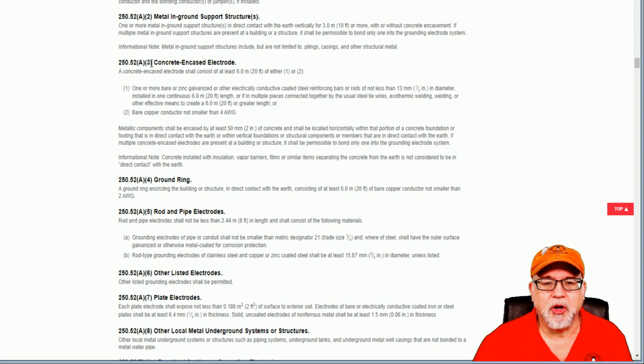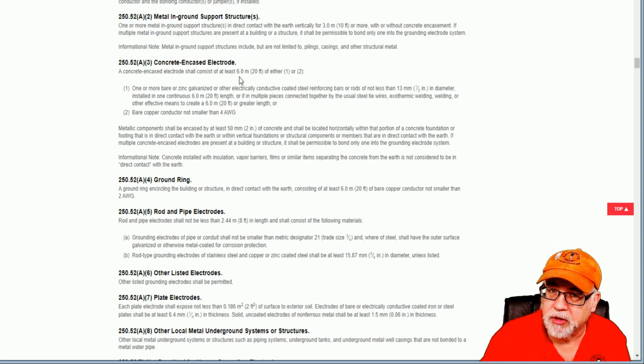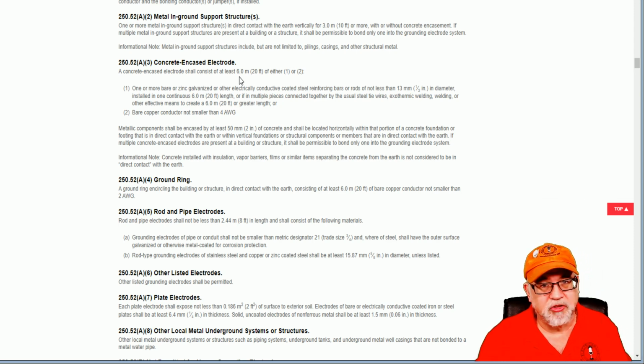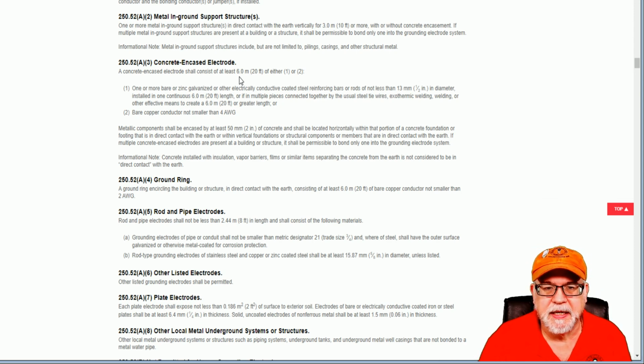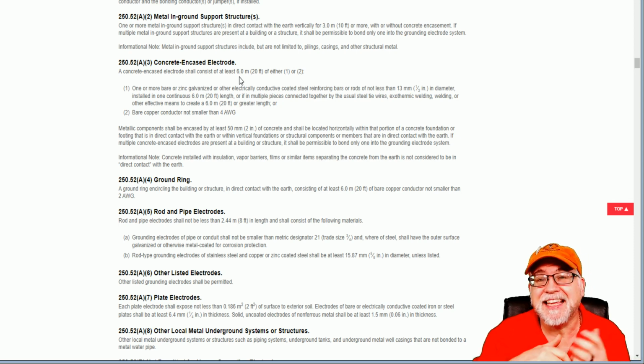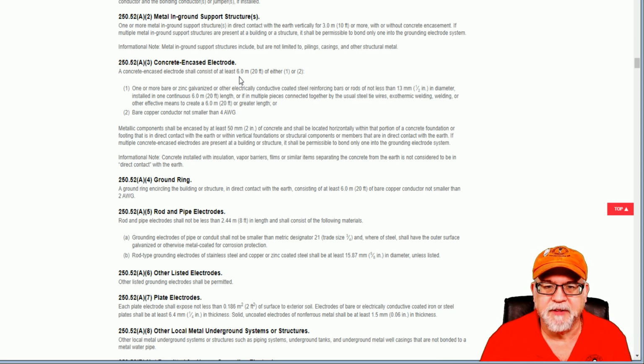Now, when it comes to the third one, which is a concrete encased electrode, again, it's inherent with construction, not something that I as an electrician am going to do. So it's going to be zinc galvanized or electrically conductive coated steel reinforcing bar or rod of not less than 1/2 inch in diameter, installed in a continuous 20-foot length, or in multiple pieces that together come up to 20 feet.